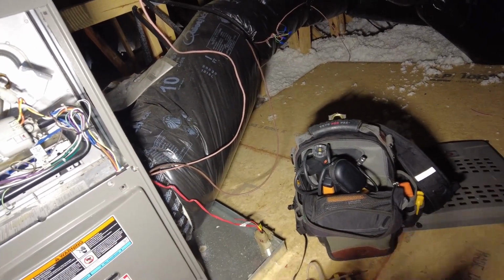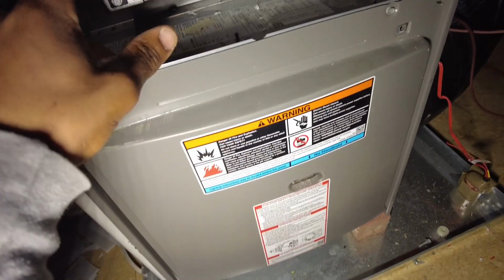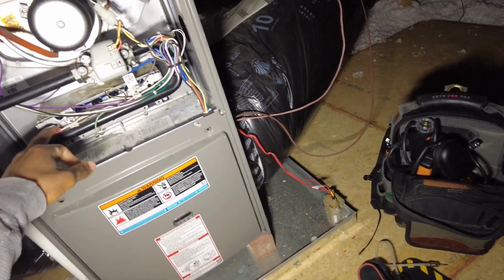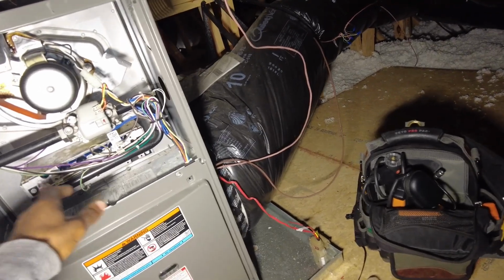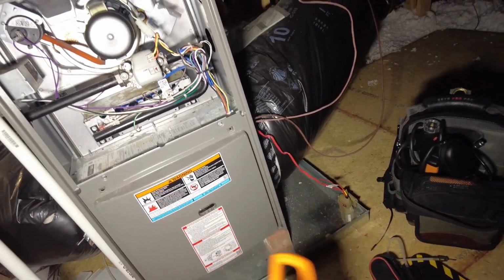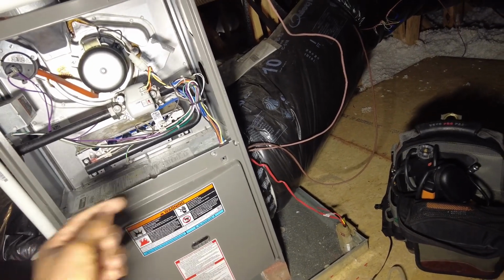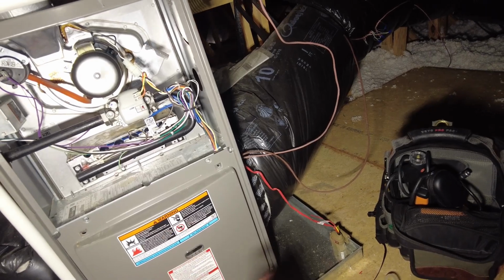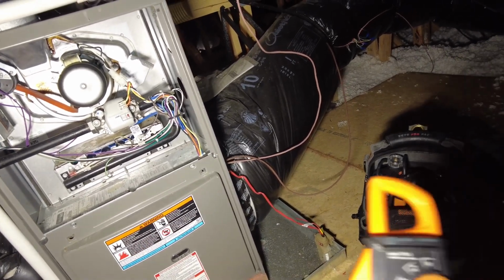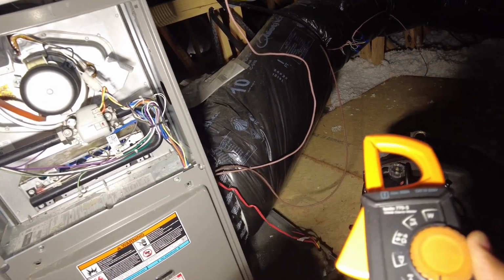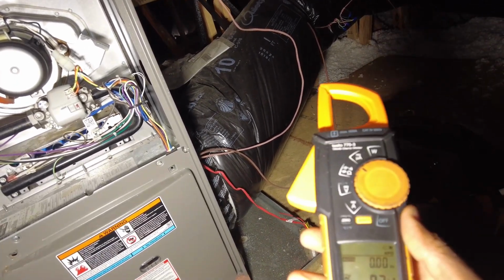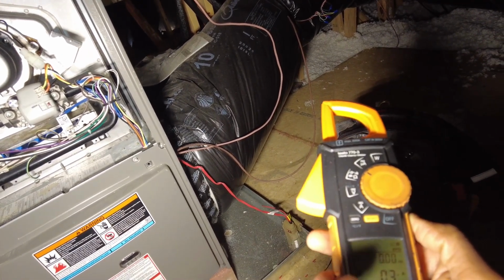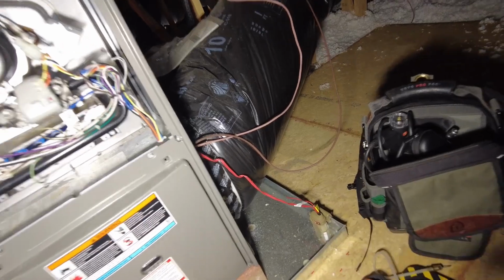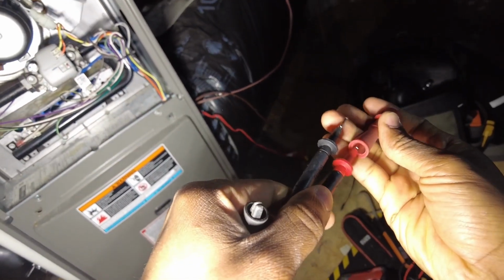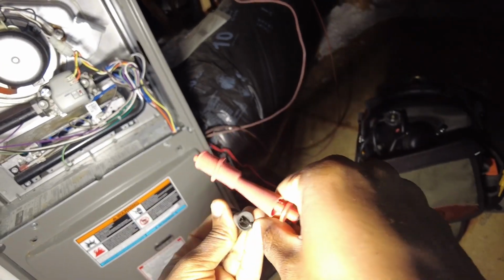Now we're going to go ahead and check our flame sensor. All right, so now we're going to check our flame sensor microamps, and that's going to be, see this here? This is connected to a wire that goes to your board, and it's going to sense the flame. It's letting the board know that there's a flame present in this burner assembly. The way it knows that is there's a rod that's immersed in that flame. It's rectifying the flame and creating a signal, a DC voltage, a small microamp signal back to the board. So we're going to put this in microamps DC, not AC, and put it in series, just run it in series. But as you can see, the system is able to run a good long time while checking everything.